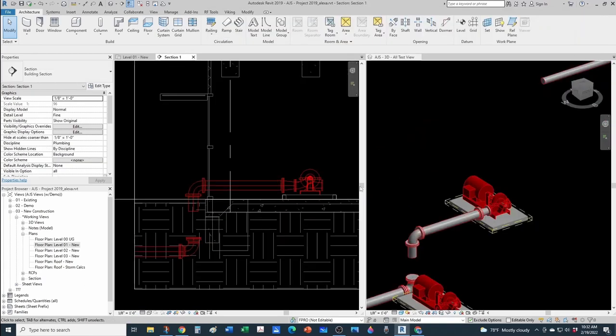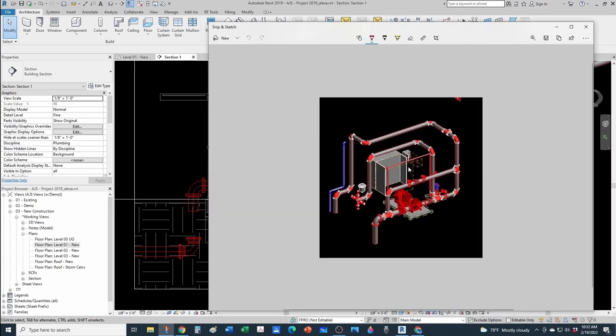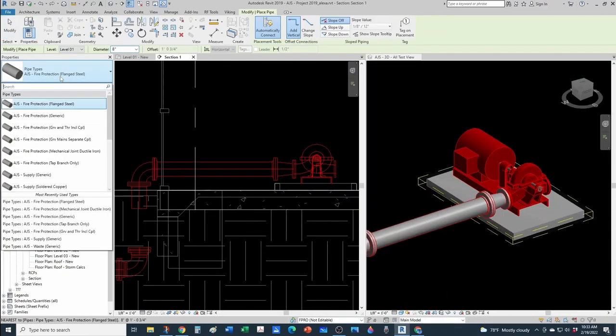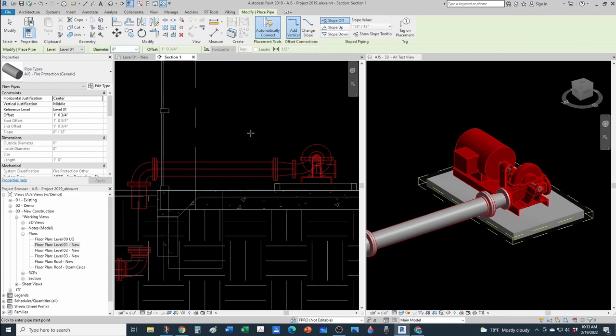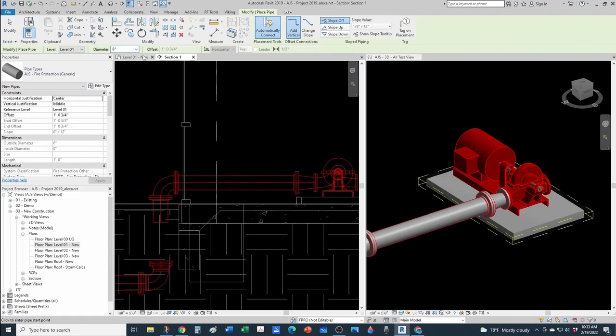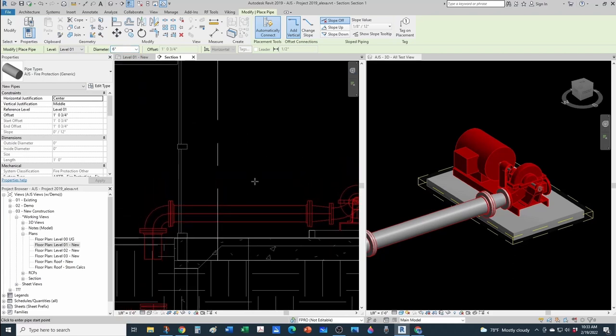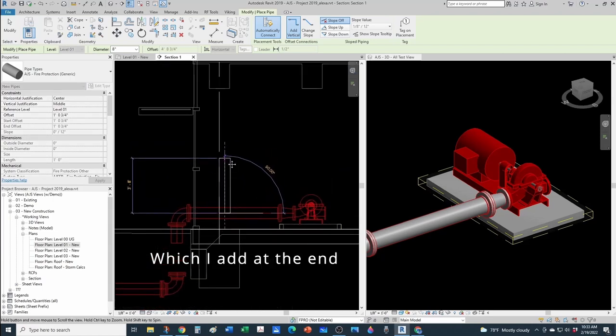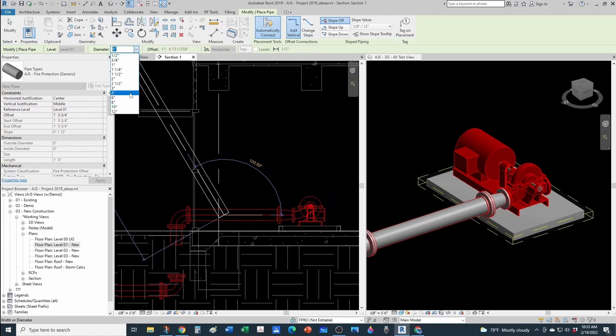Let's create our bypass, which is to be this part right here. So for that, I want to go grooved. Select here my generic piping from here, and make sure to change to 6 inches, because the bypass itself doesn't have to be 8. I can have a 6-inch bypass, and that you will see in your NFPA 20 pamphlet. So I'm going to leave a little space for my isolation valve right here, and let's take it out as a 6-inch.